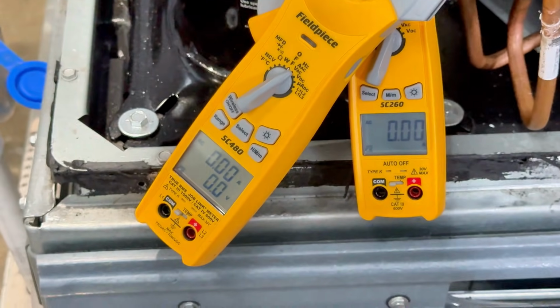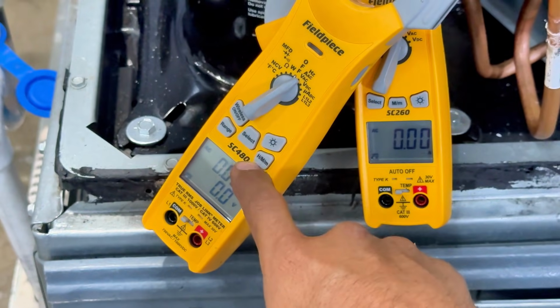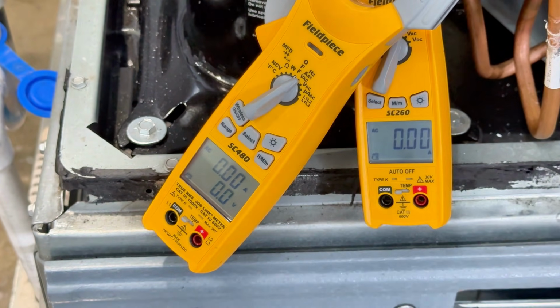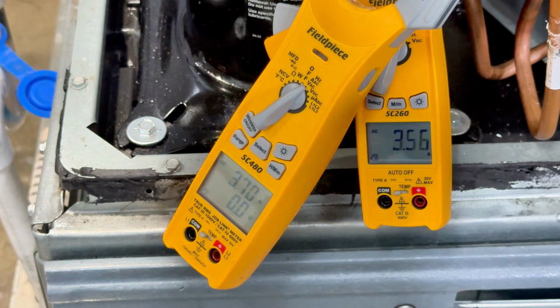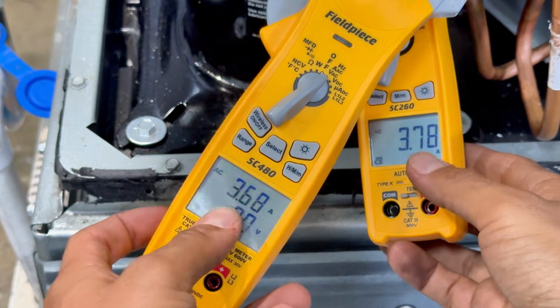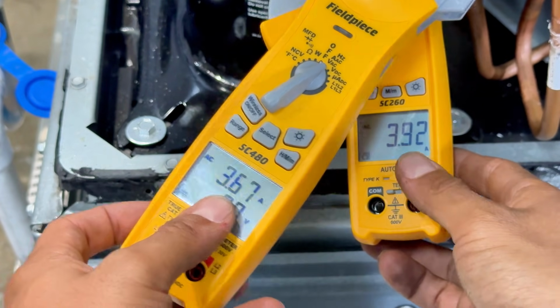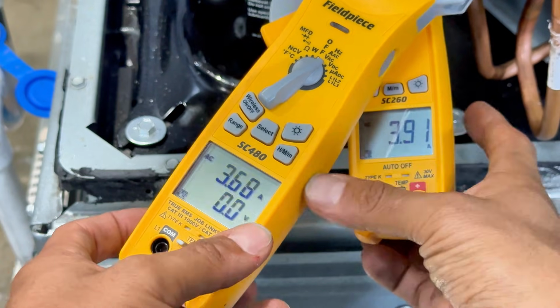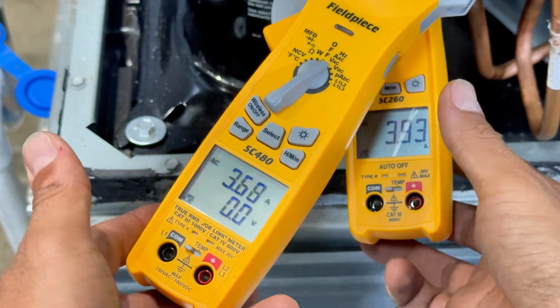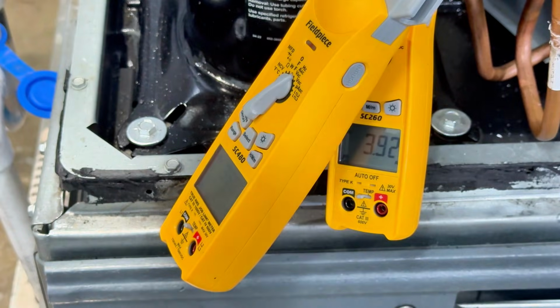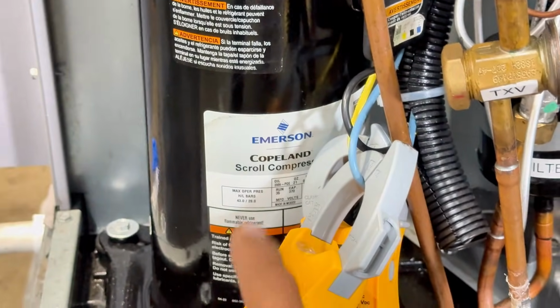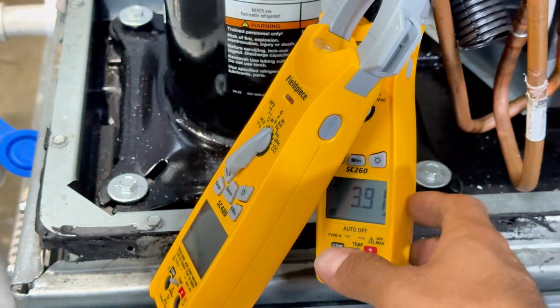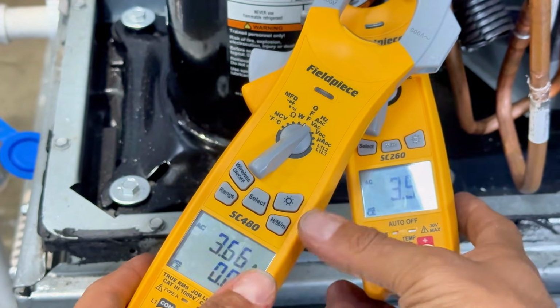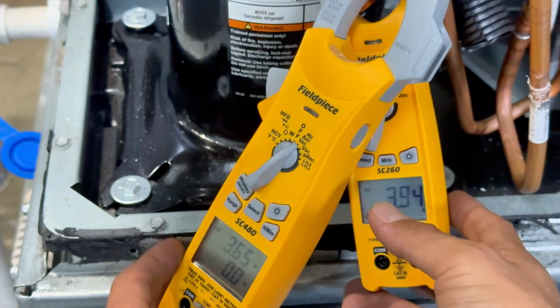Let me call for cooling and look at what's going to happen. My start is pulling about 3.68 and then 3.9. So right now, both windings are working. Of course, like I said, when you check for amp draw, you have to put it on the common. But I want to show you one quick thing. Right now we know it's on, and they're both pulling. So look at what happens when I do this.